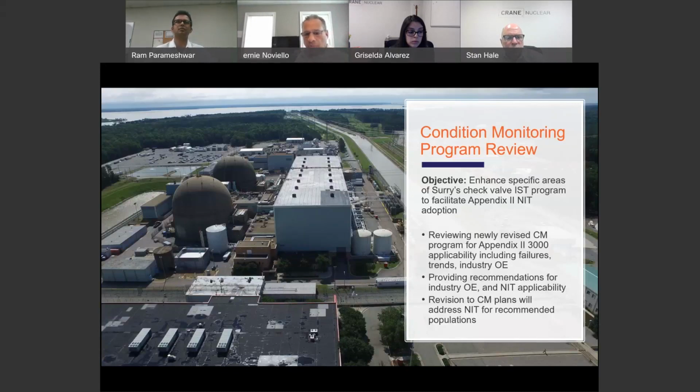Okay, so the condition monitoring program review. I was contacted by the site to do a review on the newest condition monitoring program. The objective in this case was to enhance specific areas of the existing check valve IST program, or I should say the updated IST program, which is in preparation to facilitate Appendix 2 non-intrusive testing adoption.